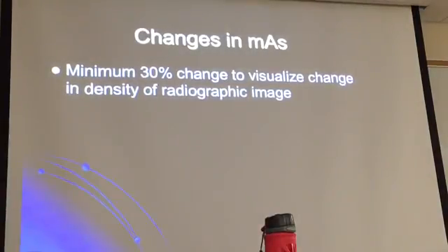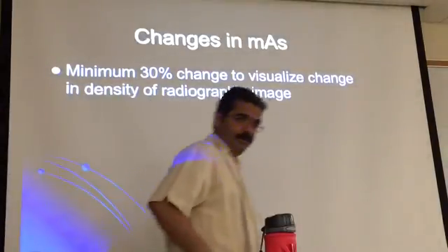So this 50% or 30% applies to film technologies and how we perceive it. With digital systems, you can try it. Go up 30% with a digital system and look at your exposure index. It will be proportional. It's not 100% effective, but it will go up about 30%. The exposure index, your S number.